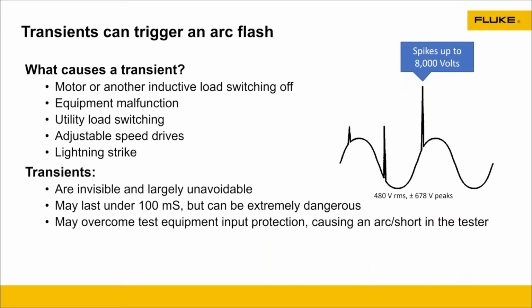And why is that? Because part of that is transients. Not too many people know about transients. Transients are actually a spike in the sine wave that's coming out. Say you're working on 240 volts, you could actually have an 8,000 volt transient run through that in under 100 milliseconds. Literally, they're very fast. It's invisible. Half the time you don't even see it. But if you happen to be touching and making a measurement at that time, you're in the circuit. It could literally go through your meter. So we want to make sure that you have the right input protection in that meter.